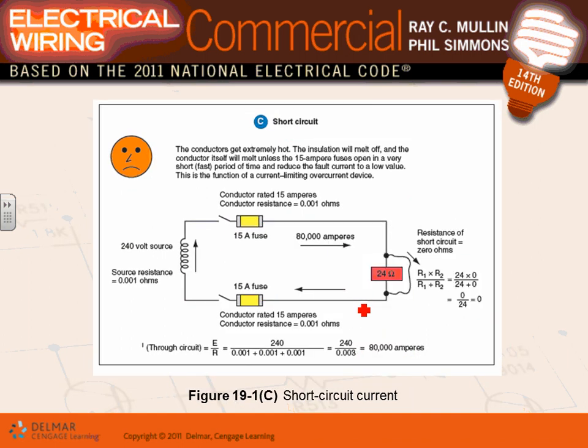Let's go to the short circuit. Look what happened with the short circuit. Now, Adam was doing his work, installing this microwave number 1, and he accidentally or intentionally took a wire and tied it hot to hot. This is hot 1, this is hot 2. This is a 240 system. Can you see that? And he went to take hot 1 and hot 2 and tie them together. Would you do that, Adam? Intentionally? I hope not.